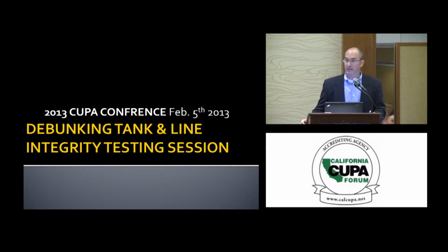The maximum tank size is 18,000 gallons. I don't know that I've ever seen an 18,000 gallon tank. That's based on a rule that was included with the certification process, where you could multiply the actual tank that you certified on by 1.5. So we had certified this method on a 12,000 gallon tank. And then the product level had kind of similar arbitrary numbers that we had done testing between 11% and 95% full. The technology and the sensors actually work at any level within the tank, but that's the certification results. It does require a minimum of 3 hours of data collection.